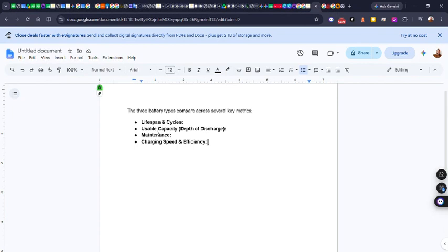First of all, when the battery discharges, it releases hydrogen gas, which makes the terminals clog, so you have to clean the terminals. The water in the tubular battery dries up too, so you have to keep refilling. So tubular battery requires constant maintenance, unlike lithium batteries.